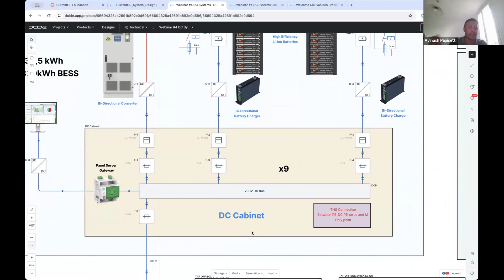Similarly, on the right side, there's a DC-DC converter acting as a battery charger. It has inbuilt protection with solid state technology. That's why the voltage on the bus side is kind of zone 3 for me. However, if I look at the AFE, it's protected by a fuse, so the bus is no longer zone 3, it's actually zone 1. But if I replace that fuse with solid state protection, it becomes zone 3, which means access for the end user is easier.